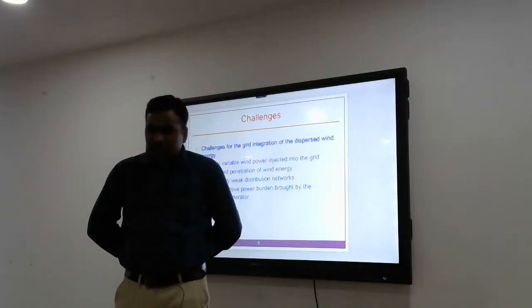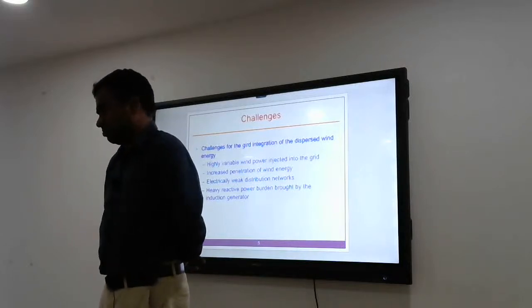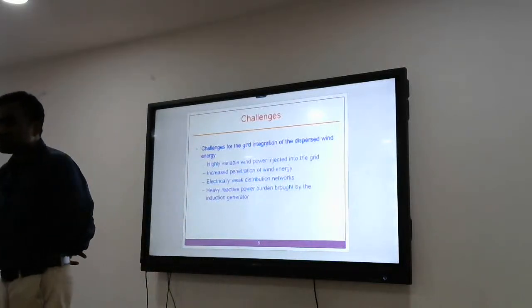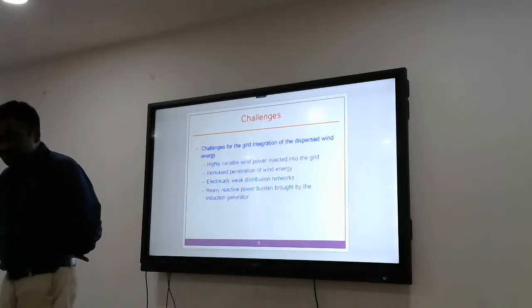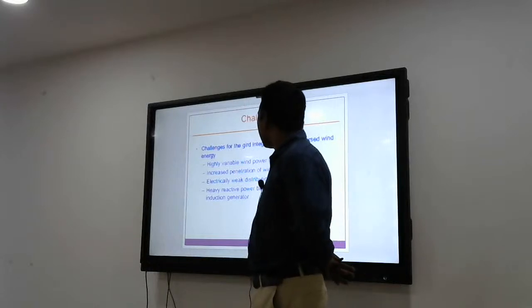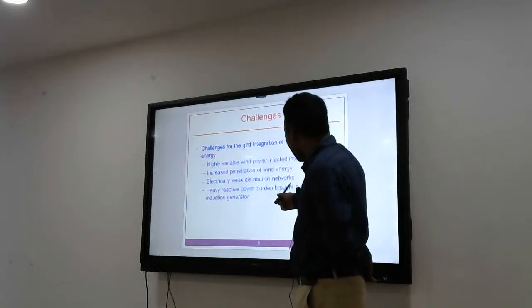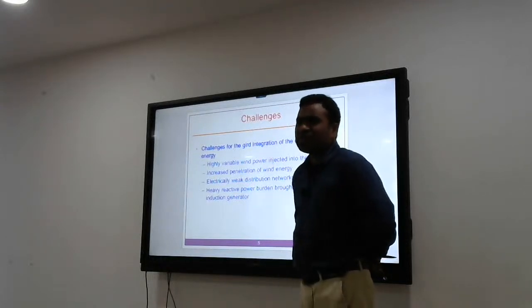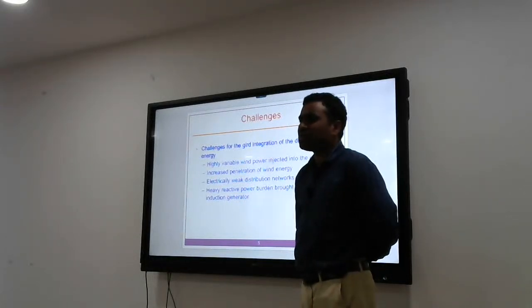So if you have high wind speed and low wind speed, then the frequency that is generated is also variable, because the number of poles is fixed. If it is rotating at different speeds, the frequency will be different. So there is a need to convert this variable voltage, variable frequency into constant voltage and constant frequency to connect to a grid. Because you have variable rotor speed, obviously you need some mechanism. This variable wind power is the problem.